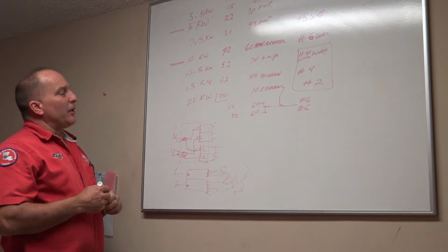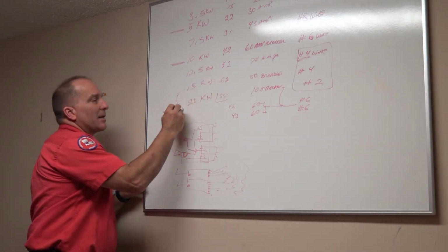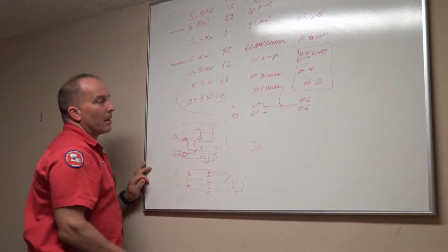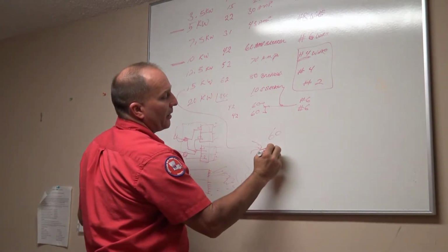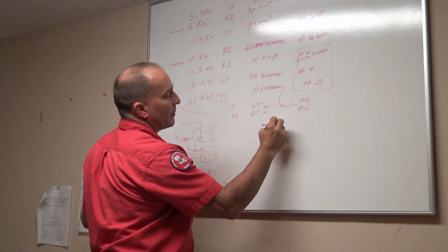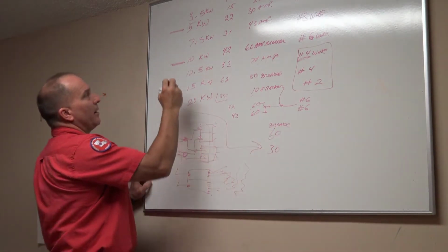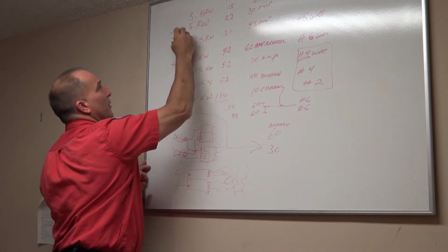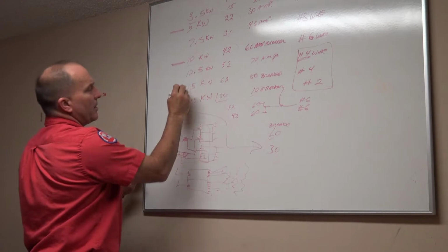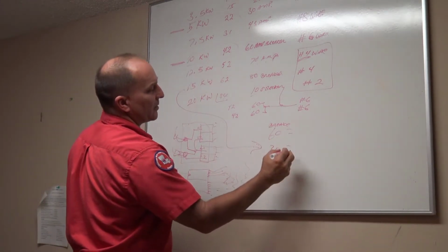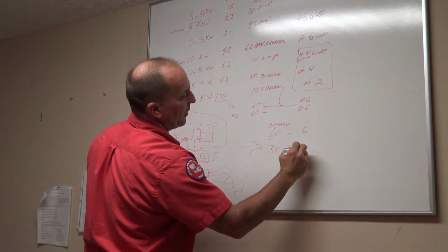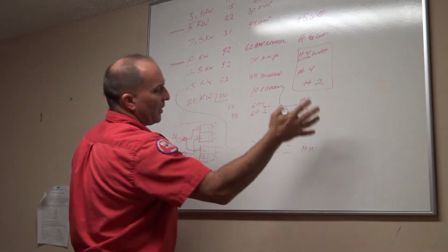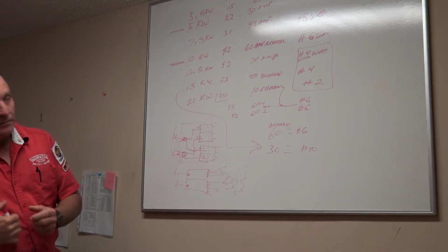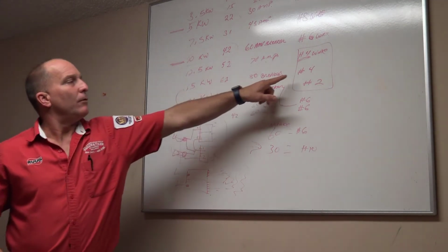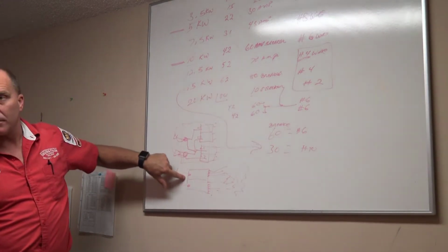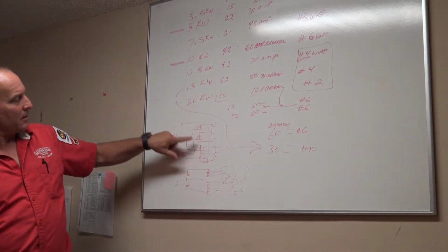15 kW. What do we need to do with 15 kW? What wire sizes and all that do we need? We need a 60 amp breaker and a 30 amp breaker, because I want to take a 10 kW and a 5 kW and make it a 15 kW, right? And then now we've got breaker size. We've got a number 6 wire here and a number 10 wire here to feed those systems. Or you can have one number 4 wire into an 80 amp breaker like this. Or it may come like this and you need it here.